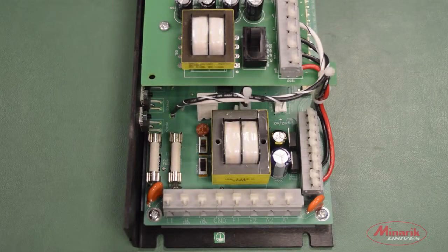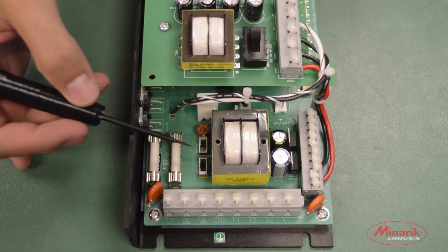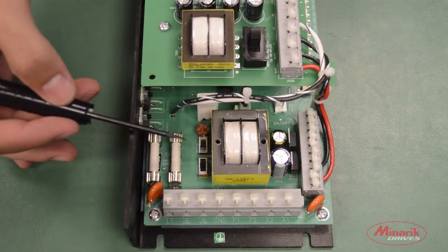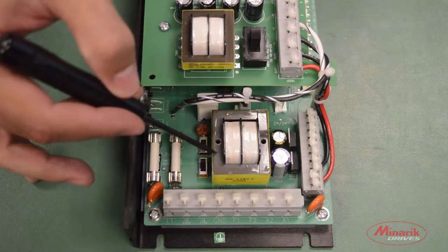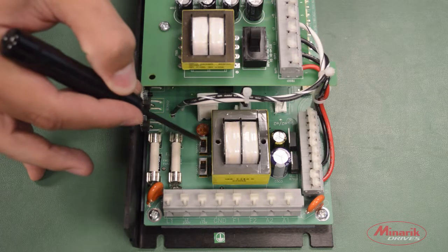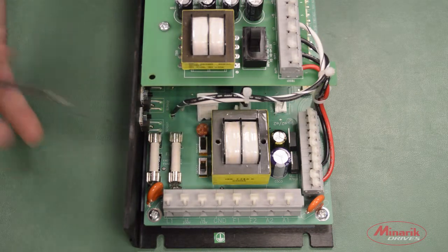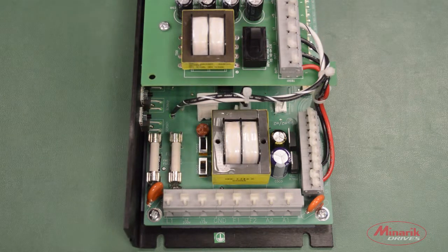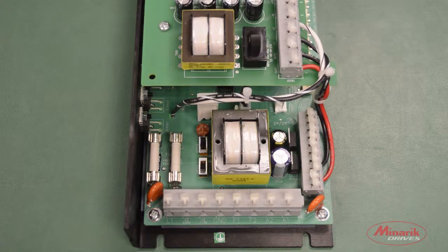The first step is to set the input and output voltage switches. The input switches are located next to the transformer and are factory default set for 230 volts AC. We're going to be using 115. There's also an input switch located on the PCM card, which is factory default set for 230 as well. So we'll move that to the 115 position.